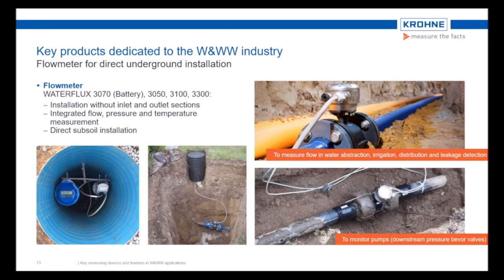Next unique feature of that key product is the possibility for direct subsoil installation, like you can see on the different pictures. This is done more and more often to save money instead of an expensive manhole which costs 3 times of the price. More and more operators exclude the flow meter from the manholes where valves and pumps are installed to have a smaller manhole which saves money.